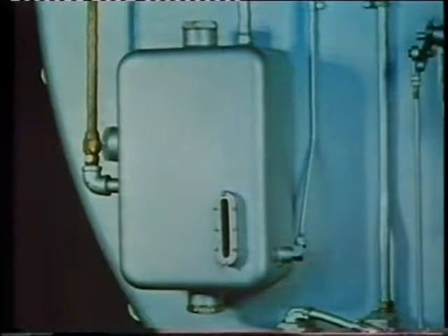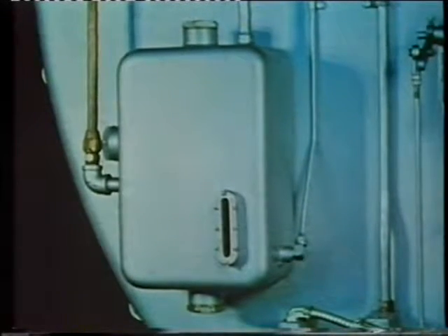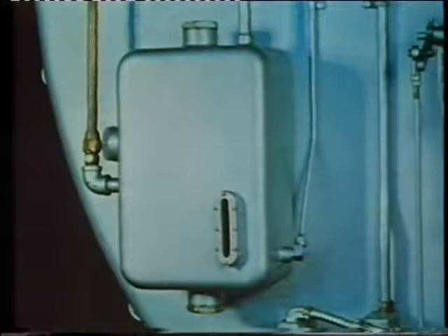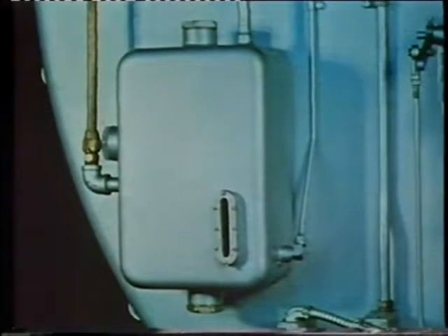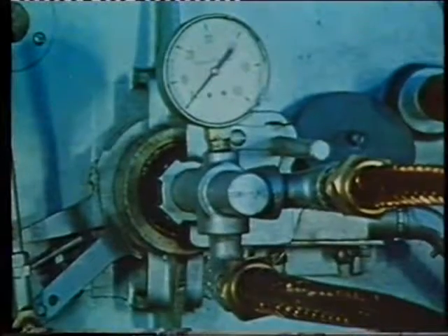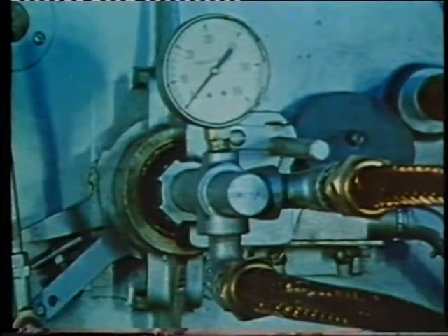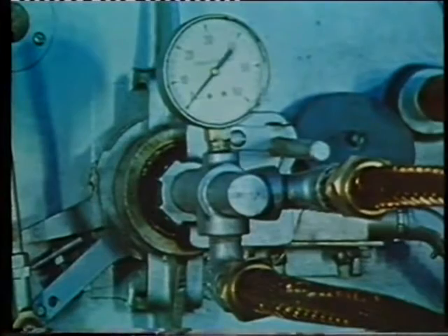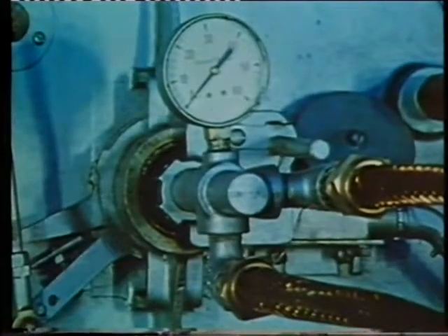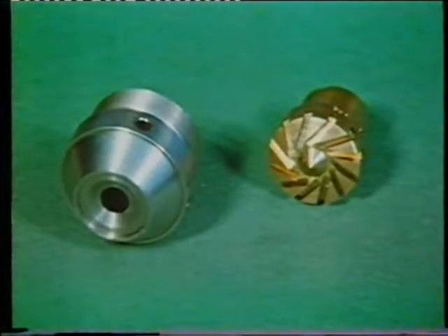The air oil receiving tank supplies lubricant for the air pump and separates the lubricant from the primary air as it passes to the nozzle under pressure. The air gauge on the burner manifold indicates the primary air pressure to the burner. The grooves in the swirler inside the burner nozzle impart a swirling motion to the primary air and fuel oil. Primary air is not to be confused with the forced draft or secondary air in the combustion chamber.